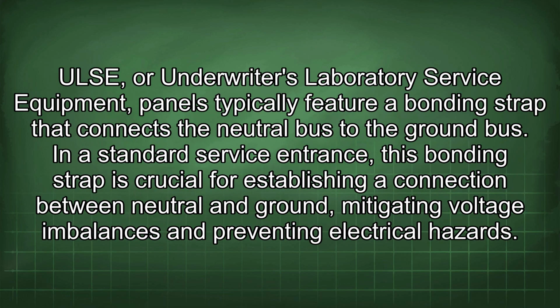ULSE, or Underwriter's Laboratory Service Equipment, panels typically feature a bonding strap that connects the neutral bus to the ground bus. In a standard service entrance, this bonding strap is crucial for establishing a connection between neutral and ground, mitigating voltage imbalances and preventing electrical hazards.